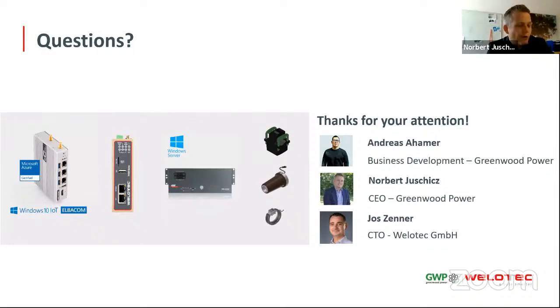Yeah, I mean the offshore power plants in northern Europe, they're usually using higher voltage levels. To be honest, they are not satisfied with 24 kV insulation levels. They are going up to 52, even 70 kV insulation level. This would need a special class of sensor for the voltage sensor. For the current sensor, it's not that important because the current sensor is always sitting somewhere around where we have a screening separation from the primary conductor.